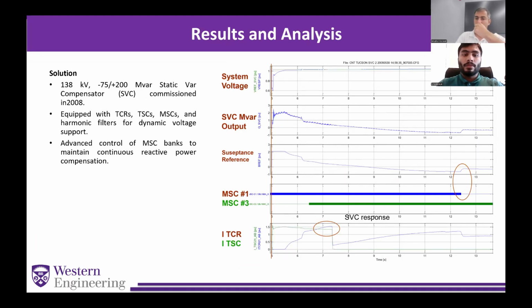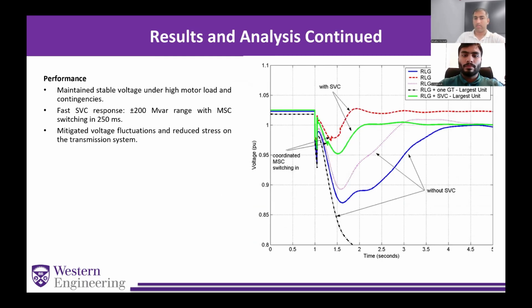An SVC of 200 MVAR, and we can also see the system voltage is now stabilized around 1 per unit. We can also see the SVC output, the MVAR output, when it injects MVAR and when it absorbs MVAR. It also shows the TCR and TSC firing angles. Can you go to the next slide, please?